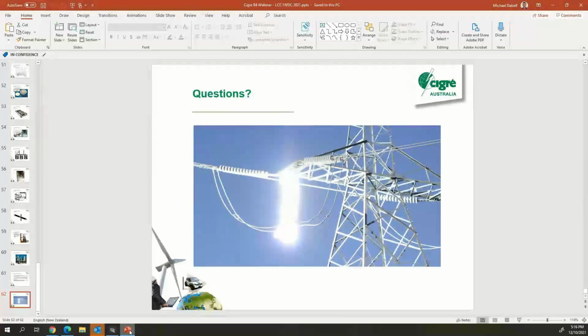Because the New Zealand link is a bipole without an earth return, have you ever operated the link, or could you operate the link if one of the cables failed, as a monopole, or would the earth return current be too high operating like that? Yes, no, so we do have the earth return scheme, and it is rated for the full current, the full monopole current. It's actually even rated for the overload monopole current. Our electrodes are rated for 3000 amps. So we're able to do the full return on the earth return with our scheme.